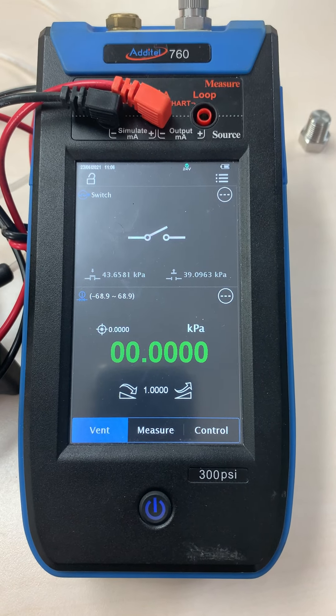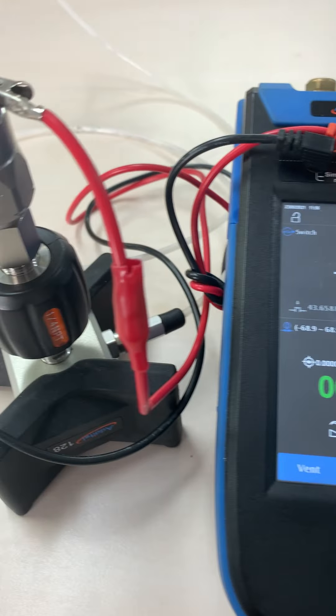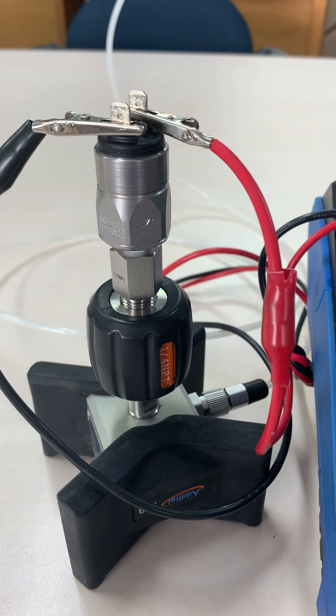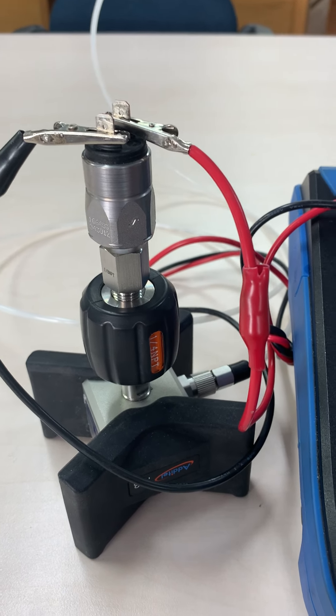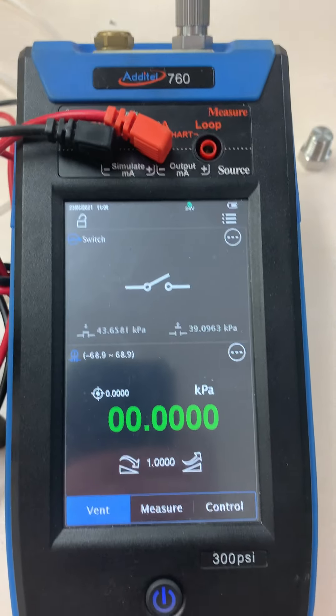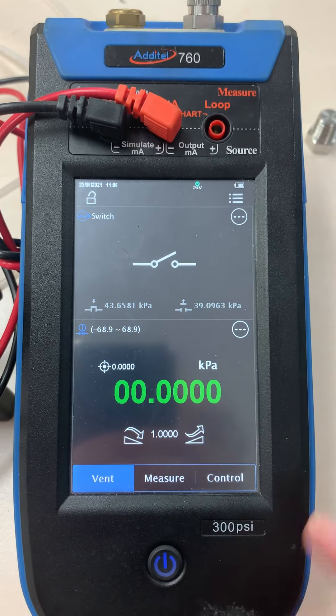One of the simple but very useful features of the Additel 760 Automatic Calibrator is the ability to check pressure switches. In this case we have a Suco switch rated at 0 to 100 kPa and it's set to be factory preset to switch at 50 kPa. Let's see if it really is.